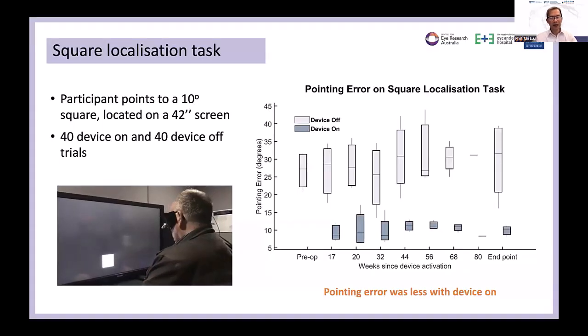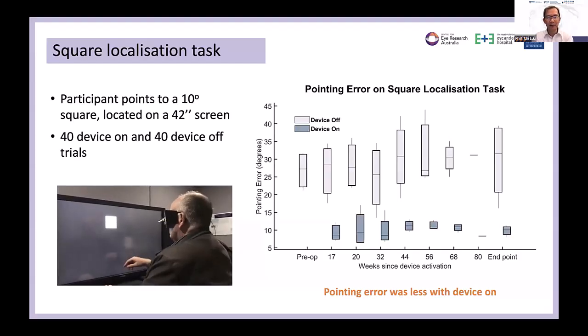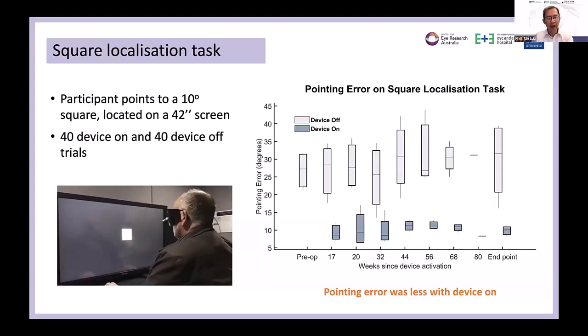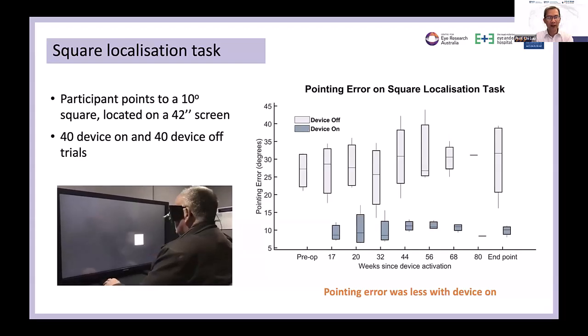So this is after training and fitting. The patients were tested on light detection, or in this case, square localization, where they need to point to the location of the square. And we measured the distance between the center of the square and the finger where they pointed, and worked out the pointing error. And you can see on the graph on the right that the pointing error is much less when they use the device compared to when the device is off.